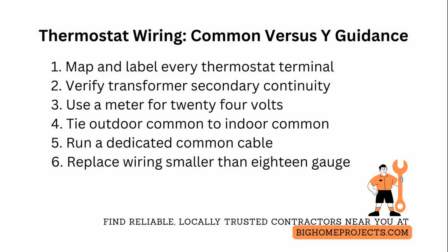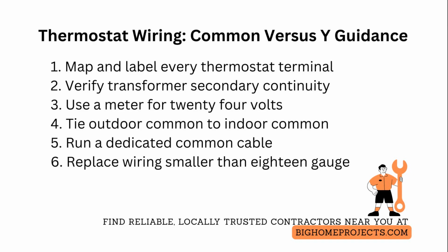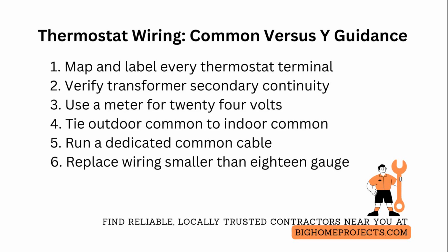For setups using a single transformer, tie the outdoor unit common to the indoor common at the transformer secondary to prevent backfeed and ghost calls. If there are separate transformers, install an isolation relay to prevent damage from multiple secondaries.